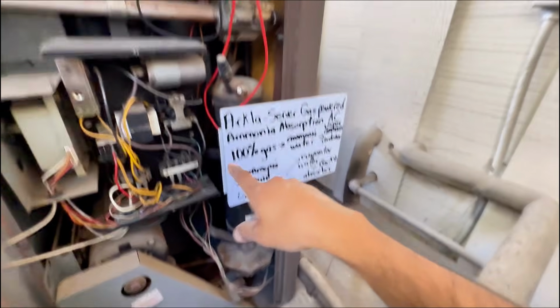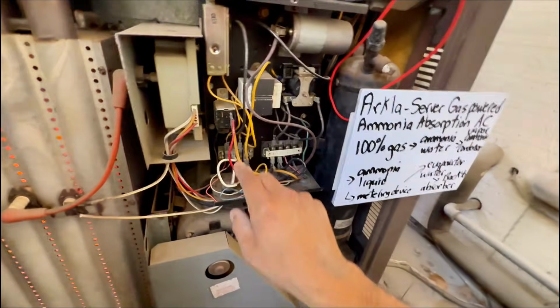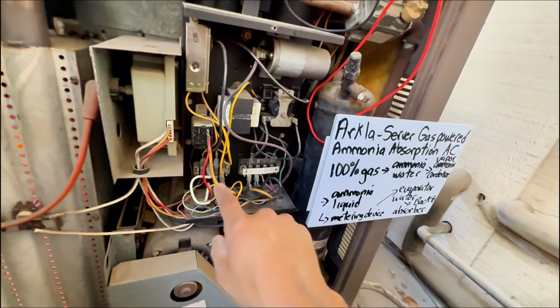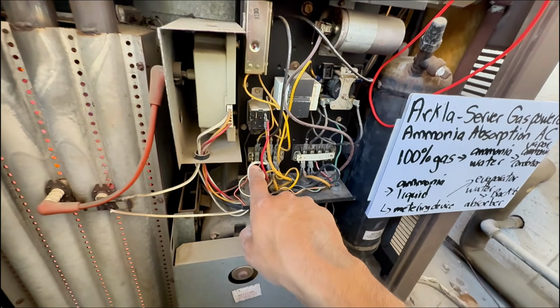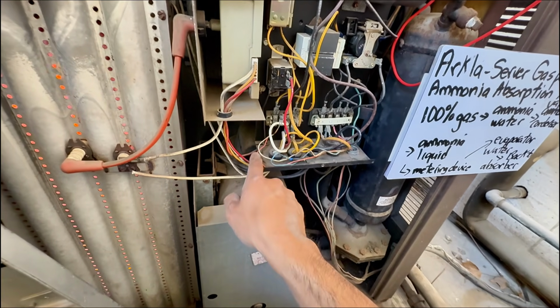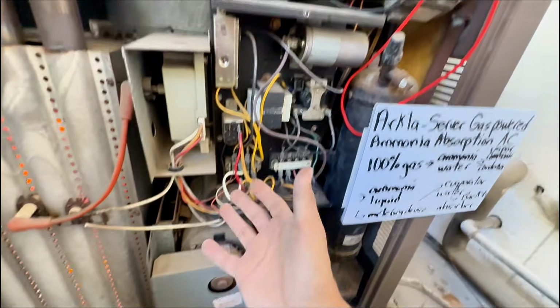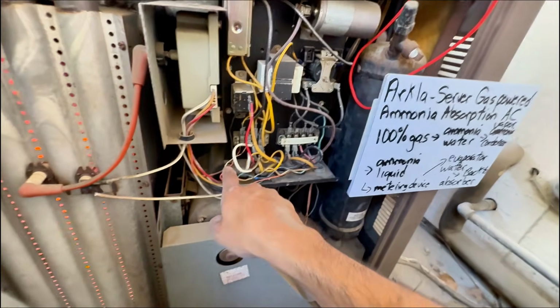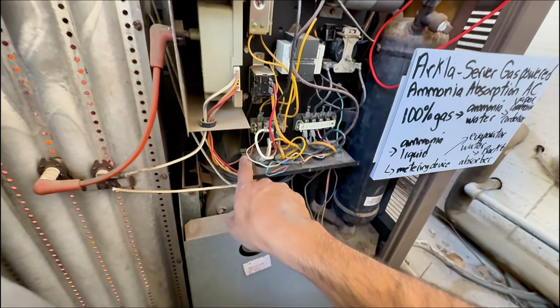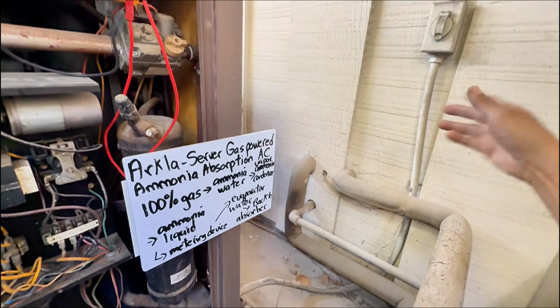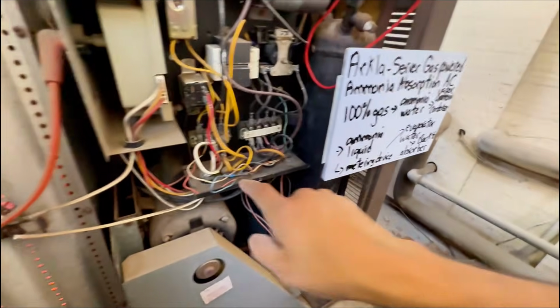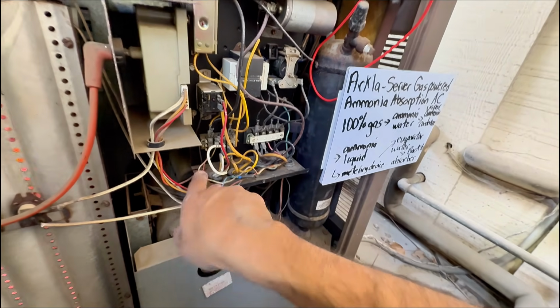So the way this works, you have your high voltage, of course, right? Your 240 coming in here, L1 and L2. You got your low voltage, and in this case they're only using two wires, right? So you're using your R and your yellow. So really, in reality, it's just a switch, right? It sends out power from this red one here inside, and if I have a call for cooling, it comes back as 24 volts on the yellow wire next to it. So if I were to jump right here, it will turn on.